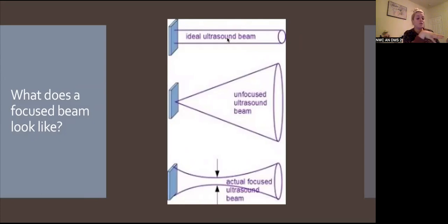Remember, what determines frequency? The propagation speed of the element and the thickness of the element. So that's how Bob puts the transducer together to determine frequency. But Bob also has to give us focused transducers, because why would we be buying transducers that are not focused? So we're going to learn about how Bob focuses the transducer.